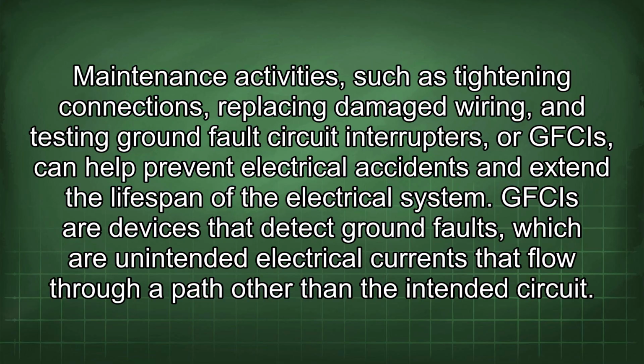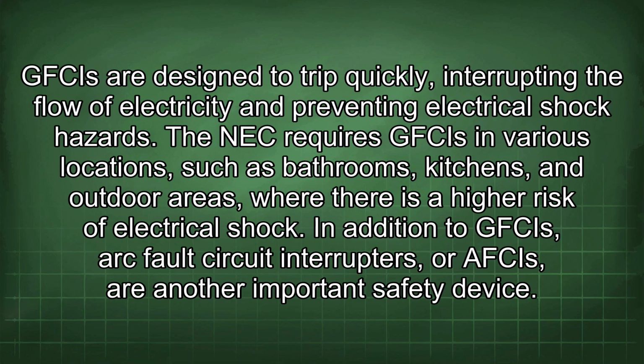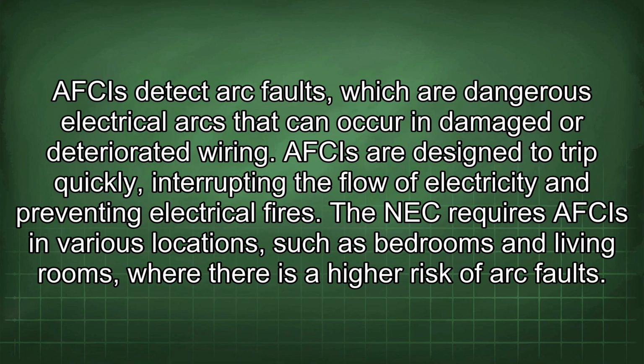GFCIs are devices that detect ground faults, which are unintended electrical currents that flow through a path other than the intended circuit. GFCIs are designed to trip quickly, interrupting the flow of electricity and preventing electrical shock hazards. The NEC requires GFCIs in various locations such as bathrooms, kitchens, and outdoor areas where there is a higher risk of electrical shock. In addition to GFCIs, arc fault circuit interrupters, or AFCIs, are another important safety device. AFCIs detect arc faults, which are dangerous electrical arcs that can occur in damaged or deteriorated wiring.